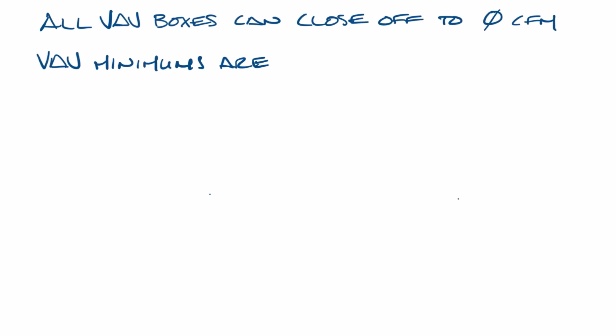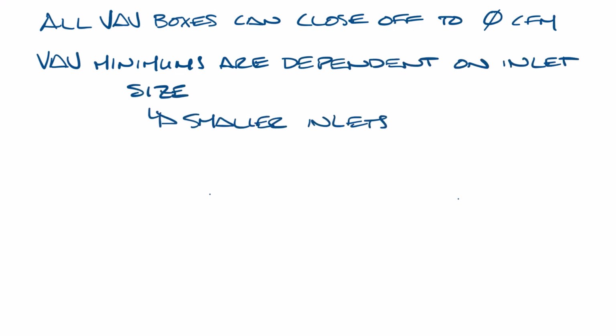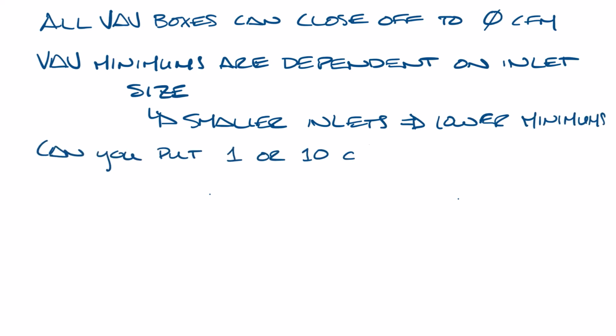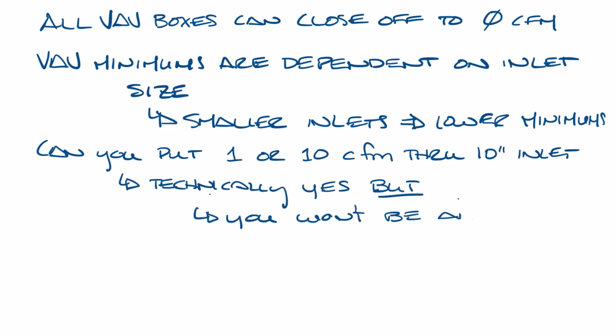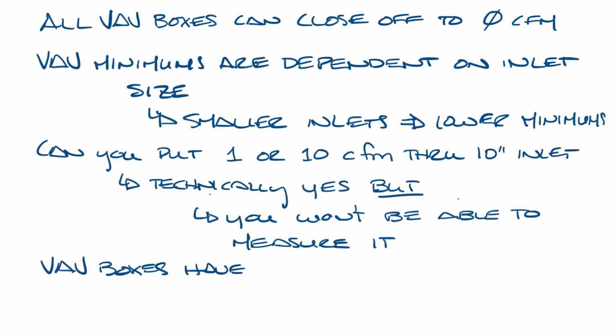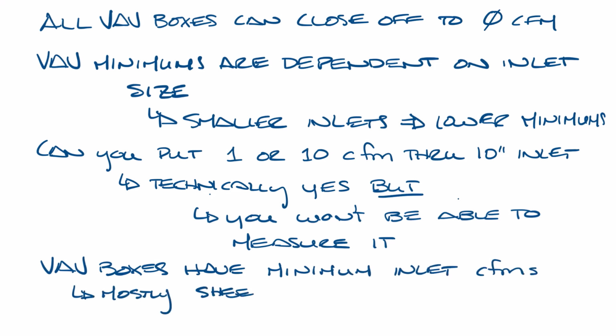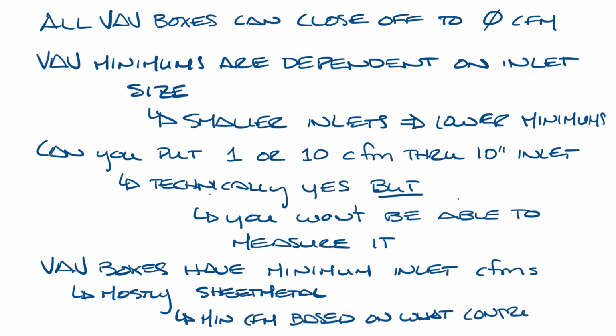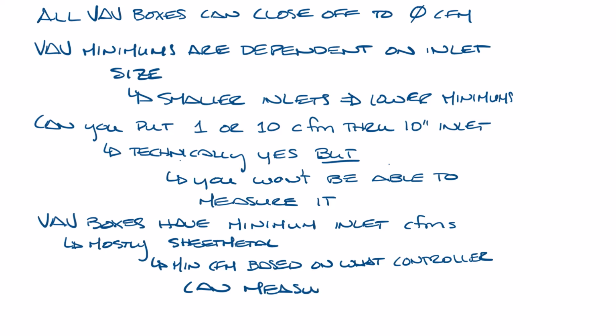All VAV boxes can close off to 0 CFM. VAV box inlet airflow minimums are obviously dependent on the inlet size, where smaller inlets will have lower inlet CFM minimums. But can you put 1 CFM or 10 CFM through a 10-inch inlet? Technically you can, but you won't be able to measure it. So VAV boxes have minimum inlet CFMs. Since the VAV box is mostly sheet metal, the minimum CFM is based on what the VAV box controller can measure, not what the box itself can handle.